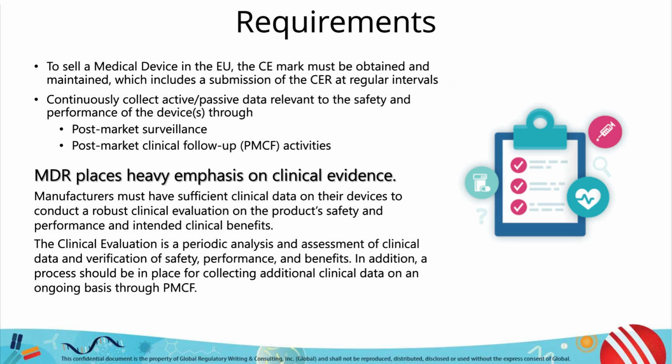When we look at clinical evaluation, it is important to remember that this is a continual analysis and assessment of clinical data and verification of safety, performance, and benefits. If these processes identify that the available clinical evidence is not sufficient, there needs to be a procedure in place for collecting additional clinical data, and this will be your PMCF.